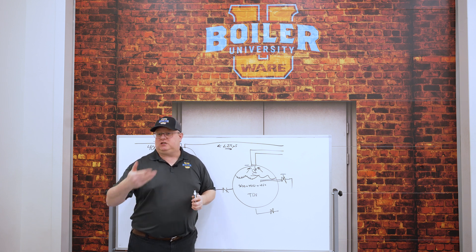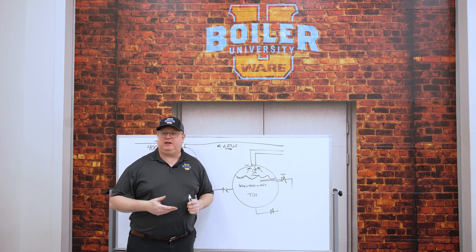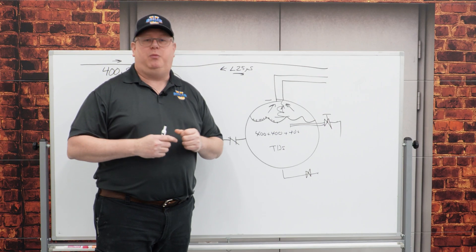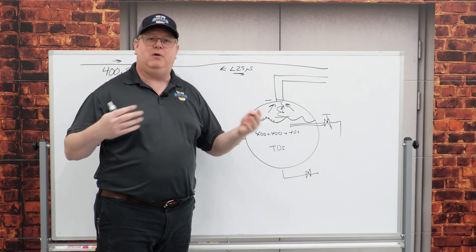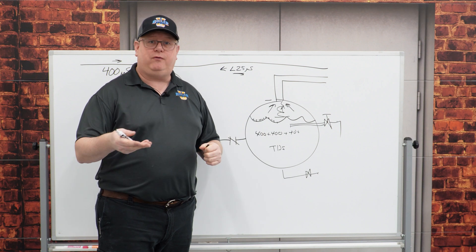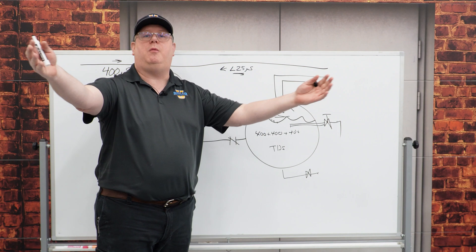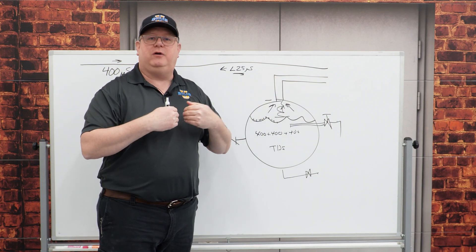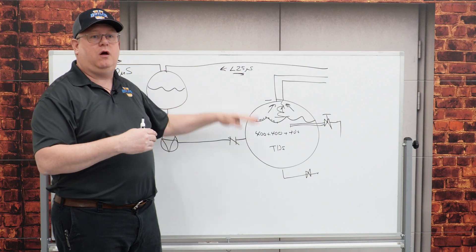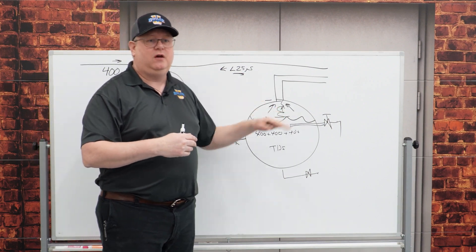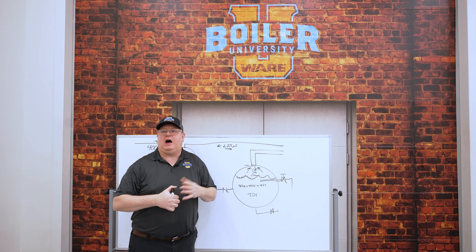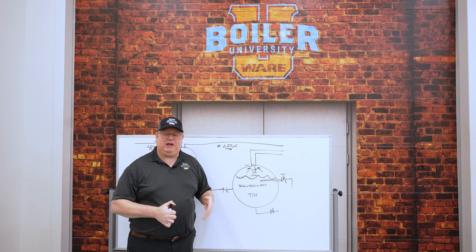Just this week we had technicians starting up a boiler — they boiled it out and the boiler was clean — but putting steam into the system, which had been down for a little while, brought back a lot of garbage from the system. So they were getting low water trips all over the place, and when we measured the conductivity it was high from those solids coming back.